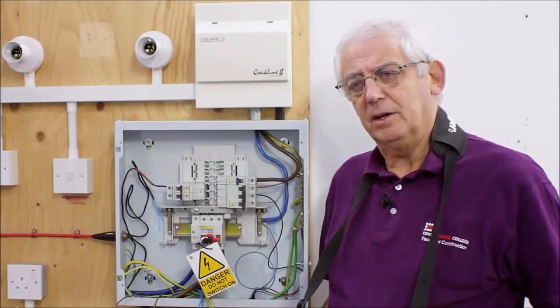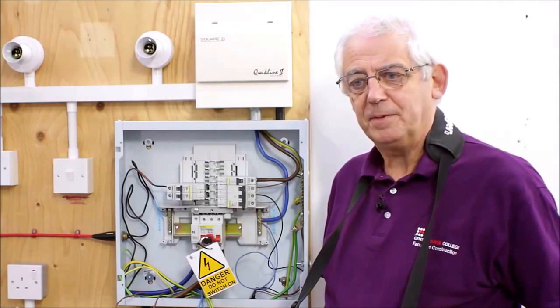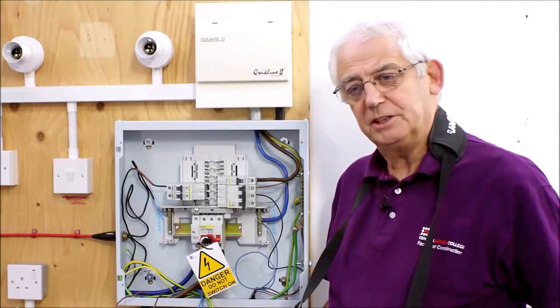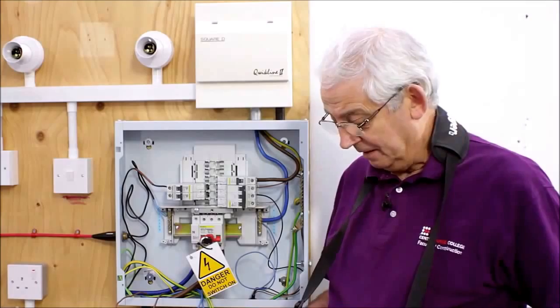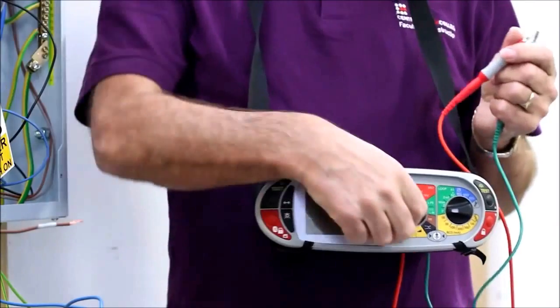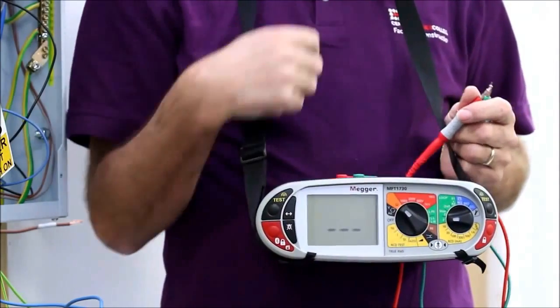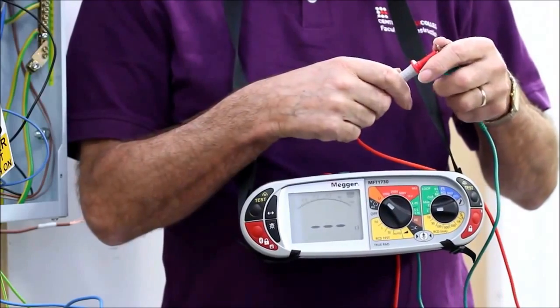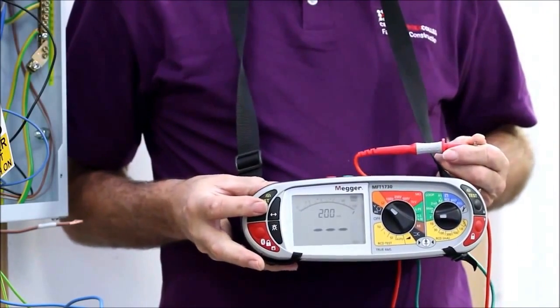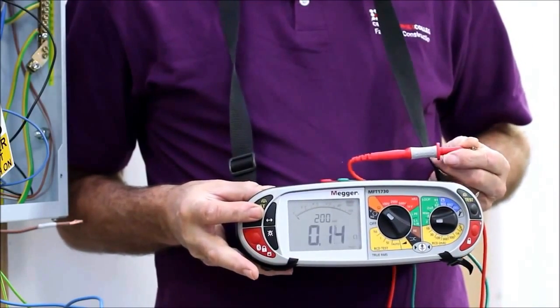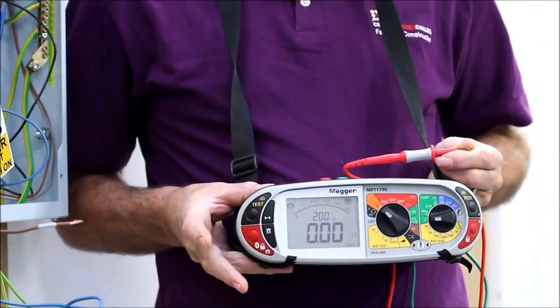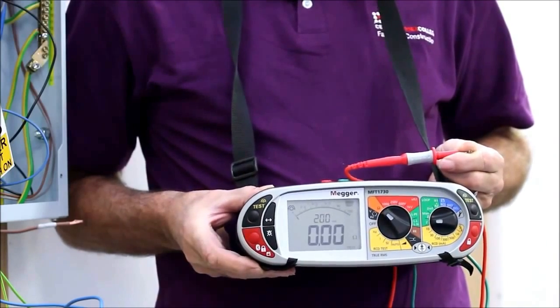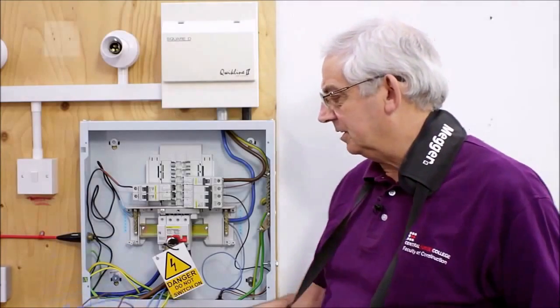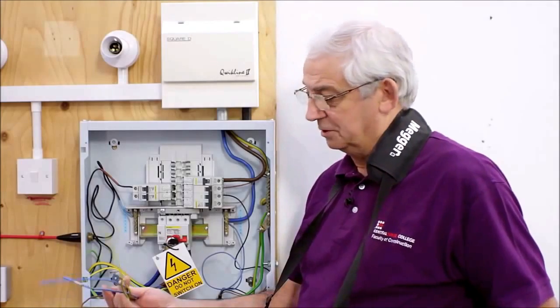We're going to carry out a ring final circuit test. And for that test we need a low resistance ohm meter with the leads zeroed. We need to turn the instrument on to ohms, join the leads together. If I push the button and then zero the leads. As you can see, I've already disconnected the leads from the distribution board.